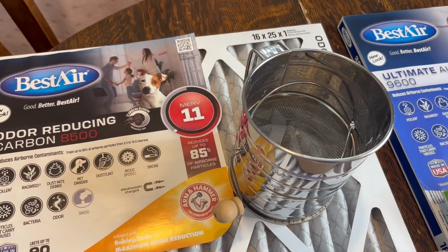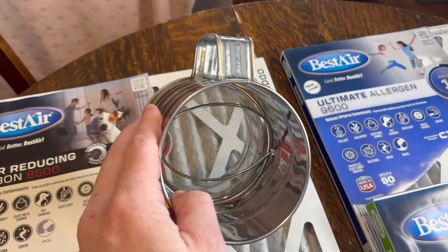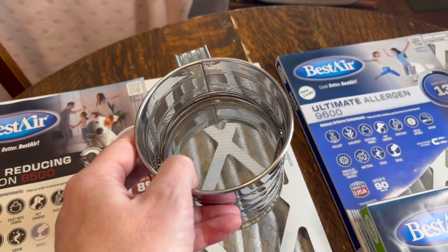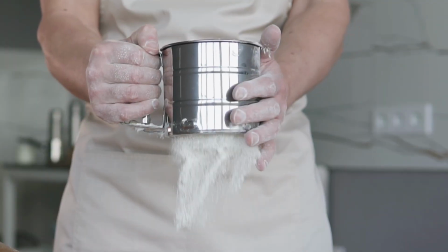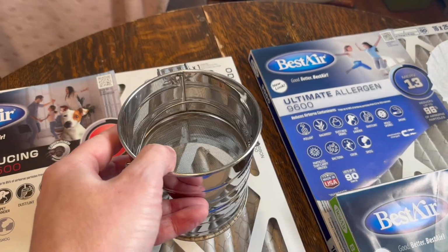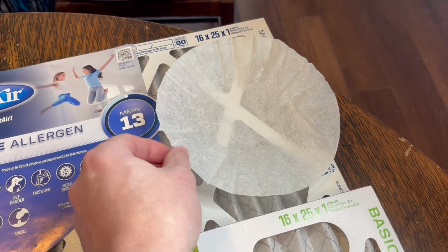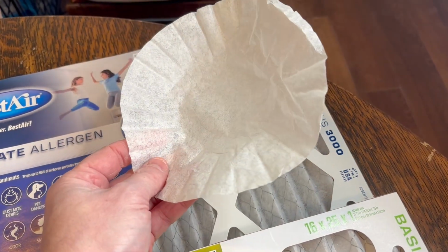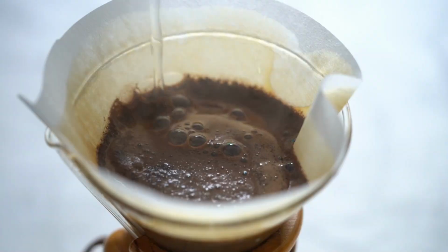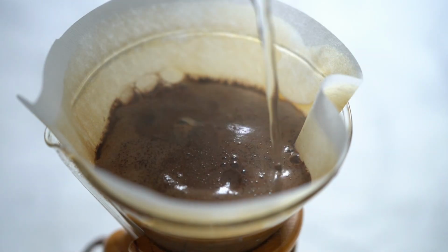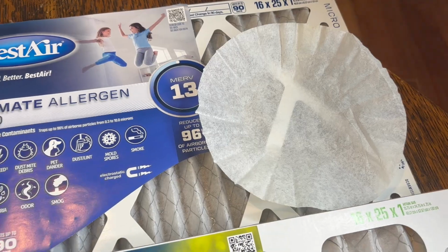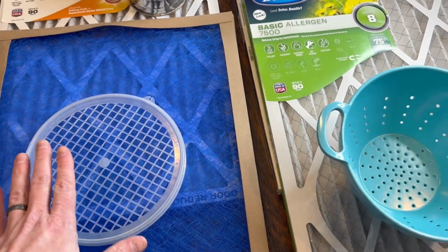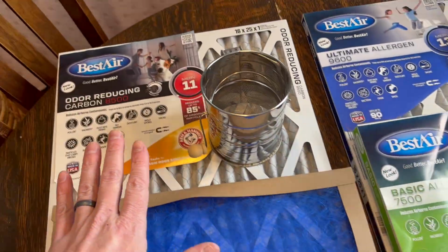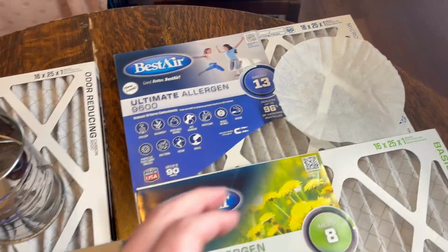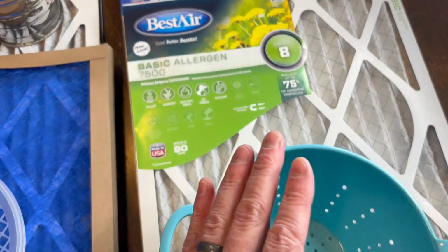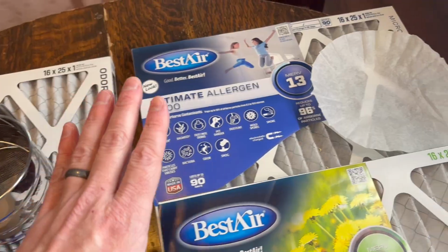And then we've got our MERV 11 filter. We've got a sifter here. This is good at removing bigger clumps of flour and sugar, but it's going to eventually allow the finer particles to pass through. And then we've got our MERV 13. This will catch the coffee grounds, but it's definitely going to be more restrictive. It's going to take a while for the water to filter through. So kind of similar in concept. As we move across the different MERVs and the different kitchen utensils, we're going to have more filtration as we get higher up, but also more restriction.